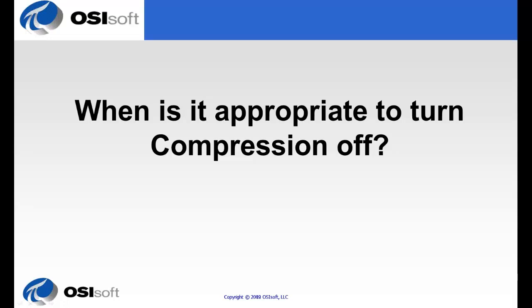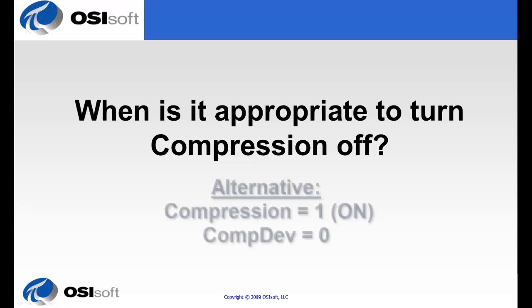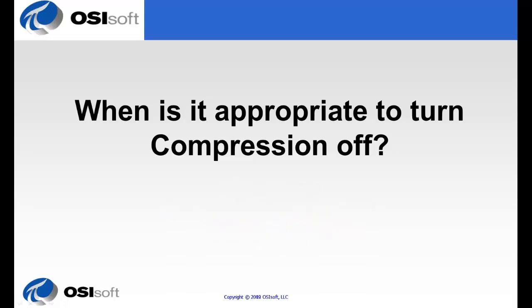A suggested better option to turning compression completely off is to set compression to on, but to set the compression deviation to zero. This means that successive identical values will not be archived. For example, a value of off that is sent to the archive and is followed by another off will not be added. This is much more efficient.